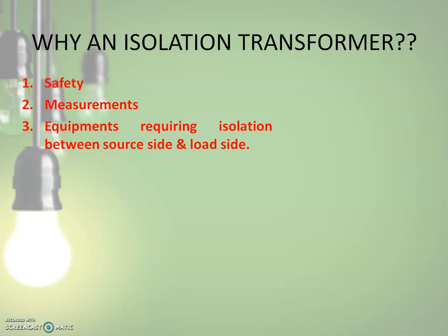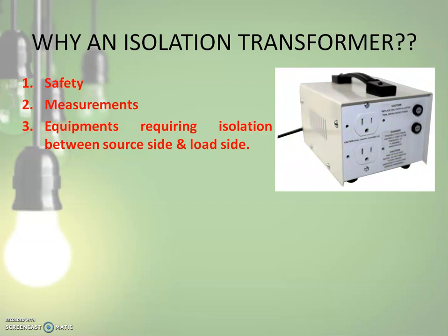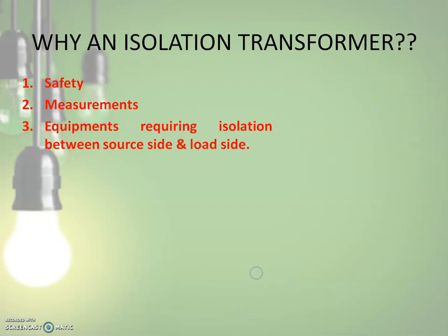Transformer suppresses the electrical noise from supplying or electromagnetic induction. This is very important in the case of sensitive devices or measurements used for medical devices. And this transformer is built with electrostatic shields, which additionally increases the electrical noise suppression. And the proper isolation transformer design avoids ground loops. Ground loops create an additional current path where the current created by electromagnetic induction can flow. And this is the main reason for noise and interference in signal, which is not acceptable in the case of devices used for medical purposes.